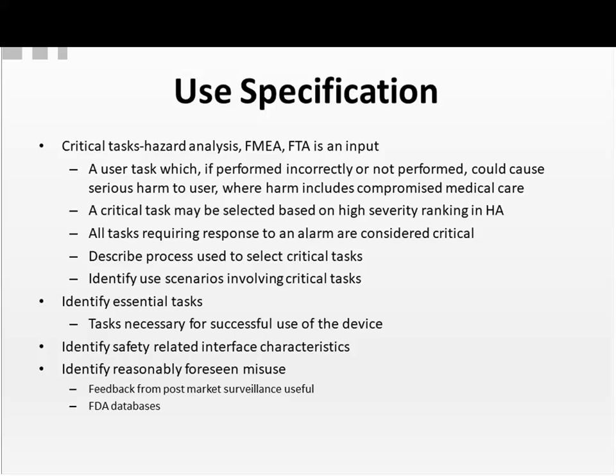You identify essential tasks. These are tasks necessary for successful use of the device, but they would not result in harm if they were performed incorrectly. It would mean that the device would not be used successfully, but there would be no harm to the patient or other user.